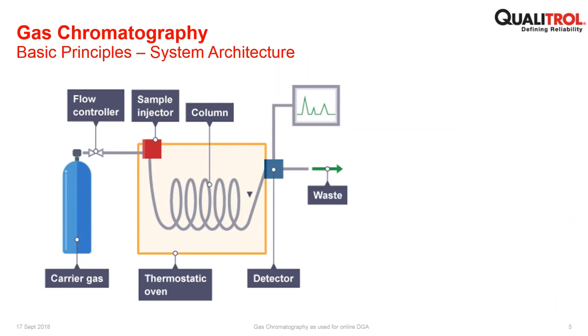First of all, some background: the basic principles or system architecture for a dissolved gas analysis system. So you've got a number of key components. You've got a carrier gas, and this carrier gas is usually one of the noble gases. In the case of our system, it is helium. In the case of laboratory systems, it is normally argon, but can also be helium. There's a regulator or a flow controller to regulate the flow of helium out of the cylinder.